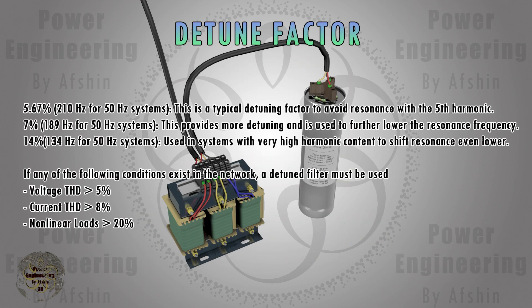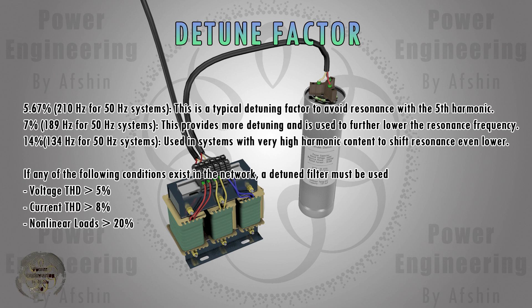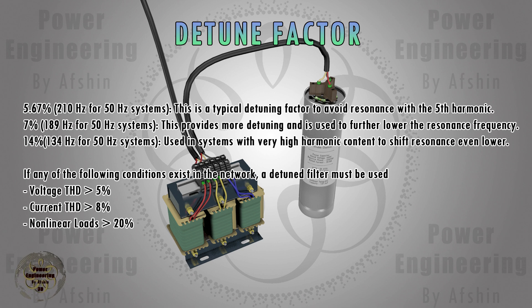The detuning factor is a percentage that indicates how much the reactor detunes the resonance frequency. Common detuning factors are 5.67%, 7%, and 14%. The detuning factor value depends on the extent of harmonic distortion in the network. A detuned reactor is placed in series with each capacitor in the PFC system.